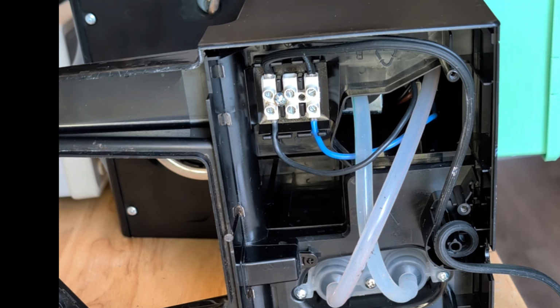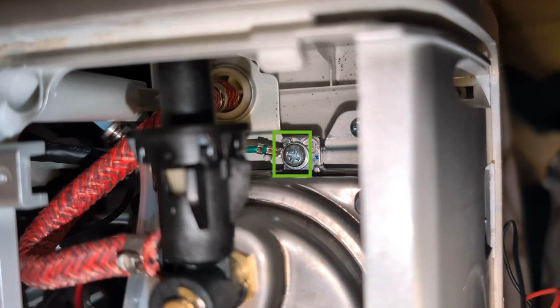Make a 12-inch 18-gauge silicone wire and attach one end to the other side of the connector block. Fish the wire up to the top of the machine. Crimp a circular or fork connector to this wire. Then screw the hoop connector tightly to the grounding point of the boiler. You'll need a M4x8 screw to do this.